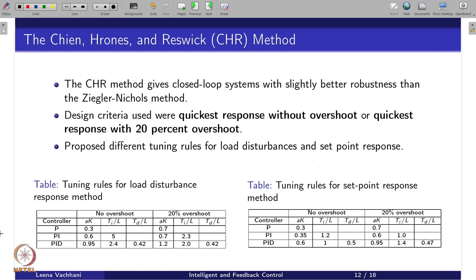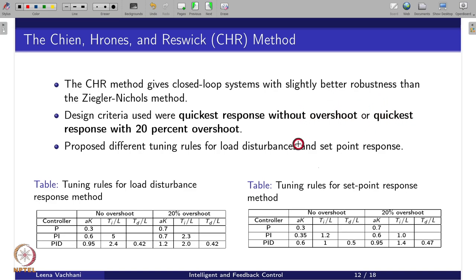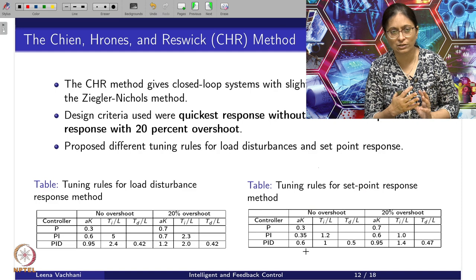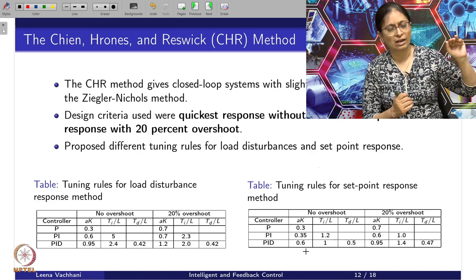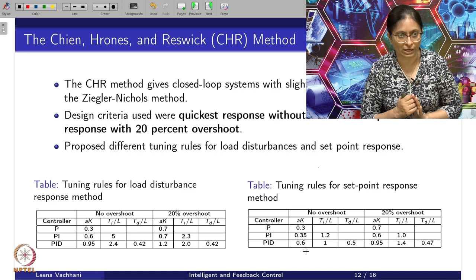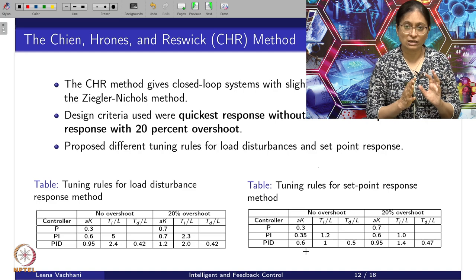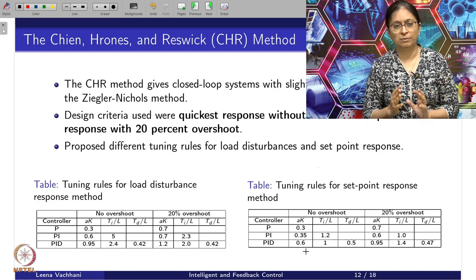The CHR method for closed loop systems will give better robustness compared to the ZN method. This CHR method is designed for the quickest response without overshoot. There are two tuning rules: one is the quickest response without overshoot, and the other is quickest response with 20 percent overshoot. The ZN method gave one rule based on step response or frequency response, always ensuring overshoot that decays with quarter amplitude decay. CHR provides tuning rules for both no overshoot and 20 percent overshoot.